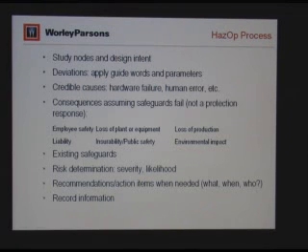And from here, we can combine all the information, and we have to decide the risk by talking about how severe this hazard, or these consequences, can be, and how likely it is for this to happen. Different equipment have different rates of failure. Pumps may fail like one time every 3 years or something.